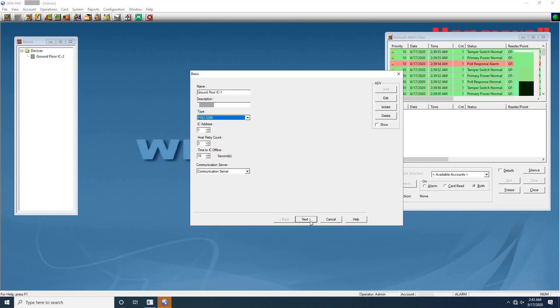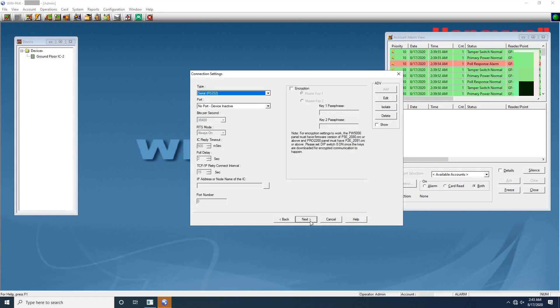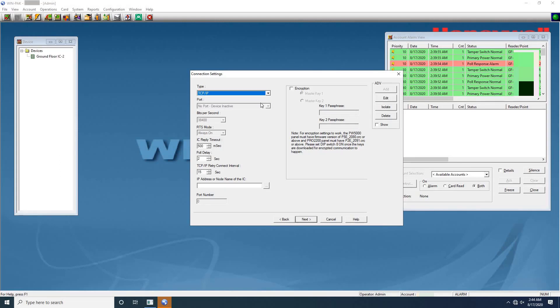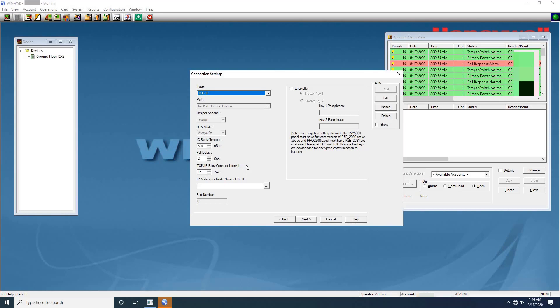In the connection settings dialog box, select the type of connection as TCP IP, which is used for connecting the P-series directly to the host computer. Next IC reply timeout. It is the duration the host computer waits for an acknowledgement after it has sent an outgoing packet. If acknowledgement is not received within the specified time, the host PC resends the packet. The host retries according to the host retry count set in the panel. The timeout defaults to 500 milliseconds, but user can set from 200 to 1500 milliseconds.